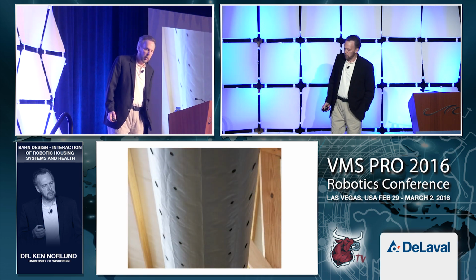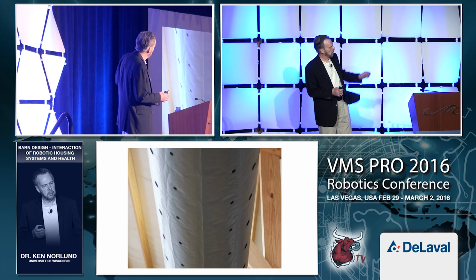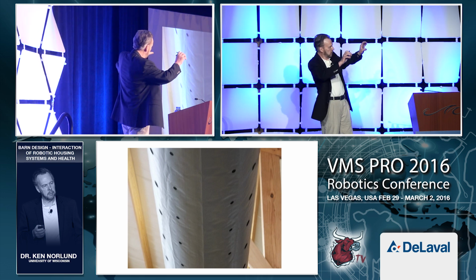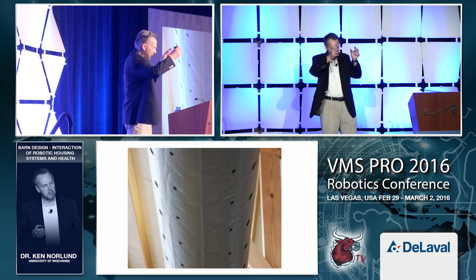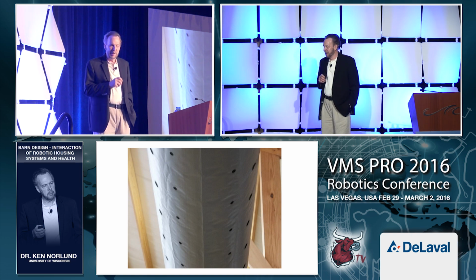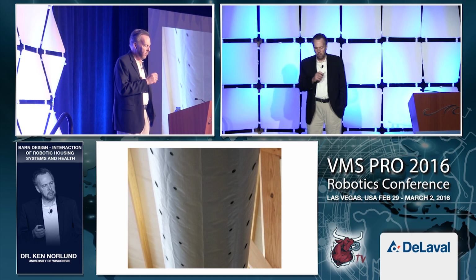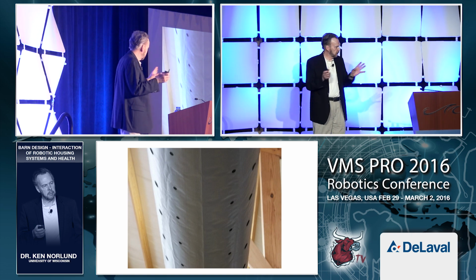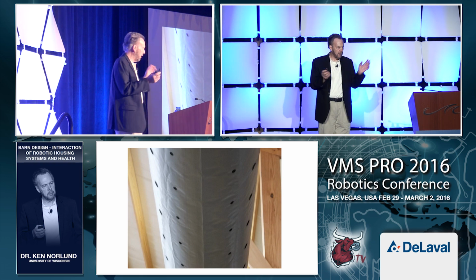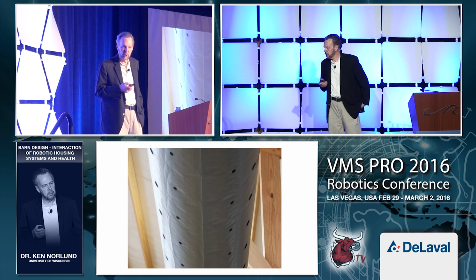The next picture will be of another tube system with 4 rows of holes, and you'll see larger diameter holes because we're going to throw air further to the sides than the ones that go straight below. So it's a custom job. I'm making that point because a number of companies are now trying to make one size, maybe 5 options of tubes, and it's simply not going to work as well as it could.